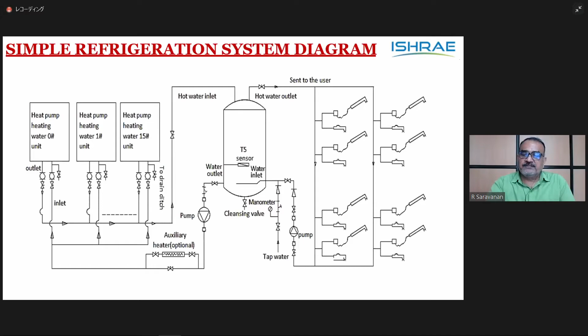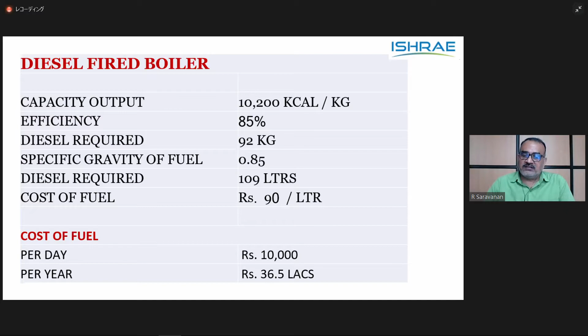When you look at the cost of the existing fuel, they're using a diesel-fired boiler. The capacity is about 10,200 kilocalories per kg. The efficiency of the boiler is 85%. Diesel required per day is about 92 kg, or 109 liters. The cost of the fuel is about 90 Indian rupees per liter of diesel. This cost has increased over the year, with a tremendous increase in the cost of diesel. So they are spending about 10,000 rupees per day. Per year, they spend about 36.5 lakhs on fuel cost to operate this water heating requirement.